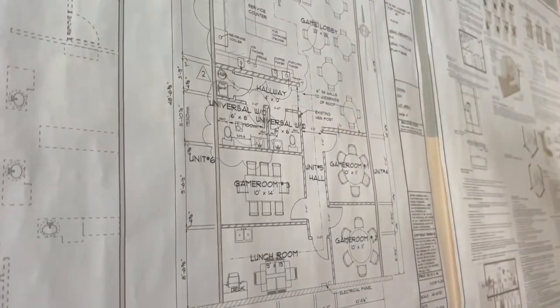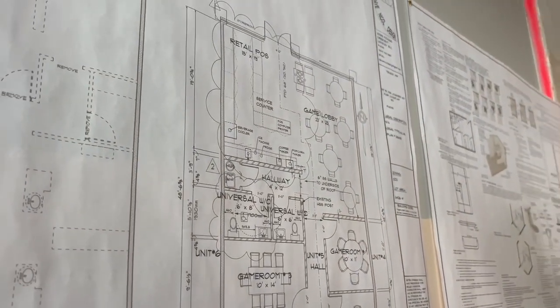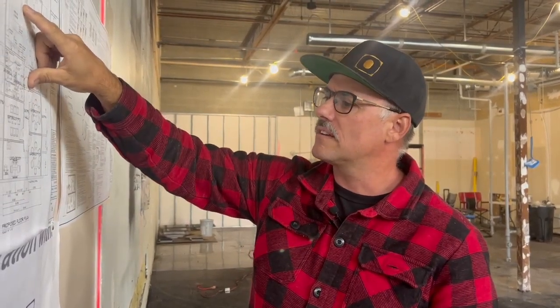So if you're a residential home builder, this isn't a requirement for you, but if you're a commercial builder, you have to look at the travel distances. So your travel distances have to add up, and I can't remember what it was. I think, yeah, this one here is 68 feet. So if you're over a certain distance, then you have to have a secondary exit. Because let's say a fire starts here, you need time to travel out to that exit. And then each of those little rooms are going to have exit signs and emergency lighting just in case there's a fire.